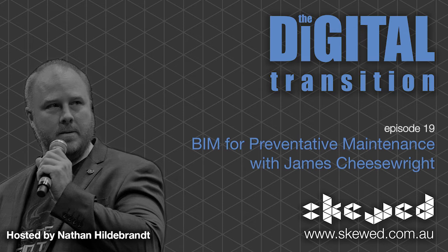But generally speaking, analytics provides great benefits for uptime, because it gives you that preemptive alert to potential failure of, say, a pump, a chiller, an air handling unit, a lighting control node, or a lift that's just making noise. We even have acoustic analytics now, which is really quite cool. Those things pick up changes or nuances before the equipment actually fails, which for a facility manager allows them to plan the change out of that potential failed equipment, or investigate it and stop it failing.